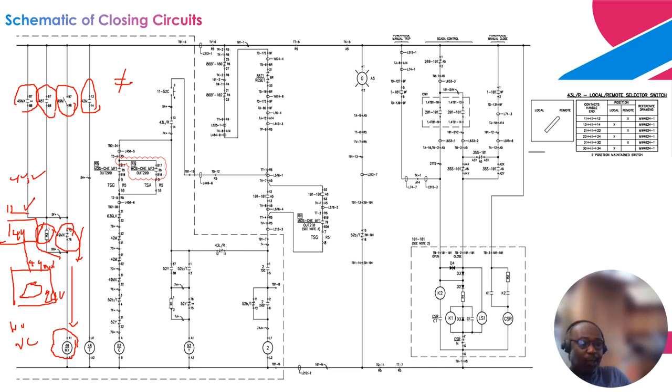This part also tells you another permissive. This is a 48T, another control relay that deals with timing. It's a timer relay coil. It requires a permissive from this contact, 42M. That is a running motor, a compressor motor. If the motor is running, the compressor is running, that contact is going to change state from normally open to normally closed. When it is closed, the wiring voltage passes through to energize the coil of this relay.